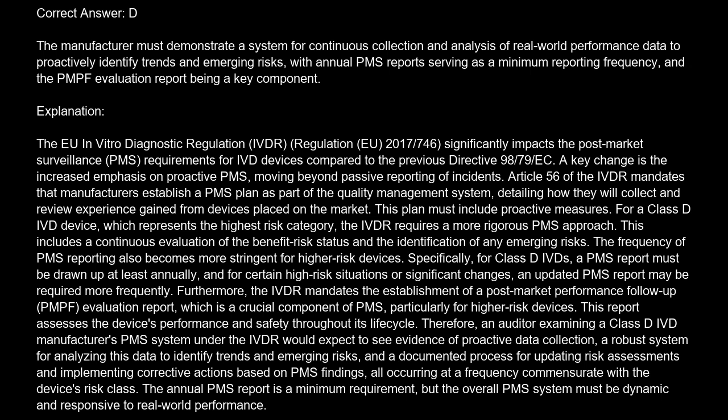Furthermore, the IVDR mandates the establishment of a post-market performance follow-up (PMPF) evaluation report, which is a crucial component of PMS, particularly for higher-risk devices. This report assesses the device's performance and safety throughout its lifecycle.